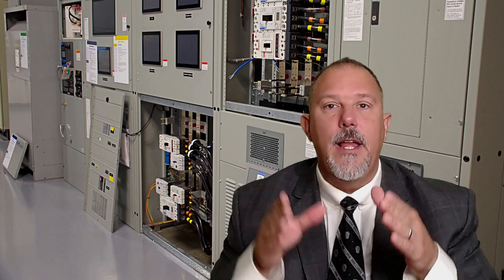So what this is telling you, recognizing the hazard, is not just understanding how much voltage is there. It's also understanding: has the equipment been installed correctly? In that case, the equipment was not installed correctly. That's an impending hazard. Severity is high. What's the likelihood? We can argue about whether or not you would hit a three-phase bolted fault. What's the likelihood of being more than 5,000 amps at that equipment? Obviously, in this example, I had much more than 5,000 amps.